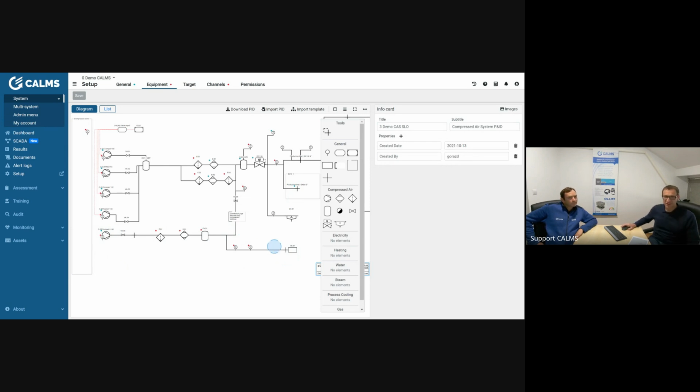So if anybody would be able to help me, because I'm really fresh here, and this Mr. Customer has a lot of knowledge and experience observing this compressor room for a long period. I know it's very difficult to jump from the questions and do the audit in a structured way. So I would suggest going through all the questions, because maybe this is not the only problem. When we entered the compressor room, we also noticed that you have a problem on the old compressors with temperature and oil leaks. So that's also one of the problems that we saw immediately.